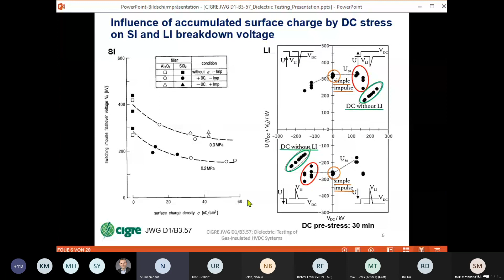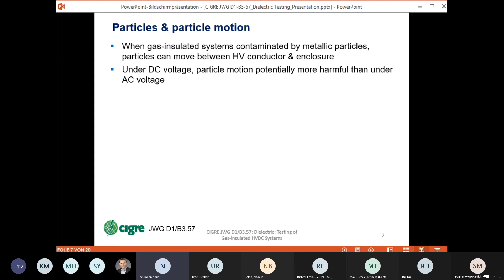The other phenomenon is the particles and the particle motion. When a gas insulated system is contaminated by metallic particles, as I said before, the particles can move between the HV conductor and the enclosure, and under DC voltage, the particle motion is potentially more harmful than under AC voltage. And we can observe two types of particle motion. As you can see here, after the lift off field strength is exceeded, the particles start to move. Either we can observe the standing motion or a bouncing motion, depending on the polarity.